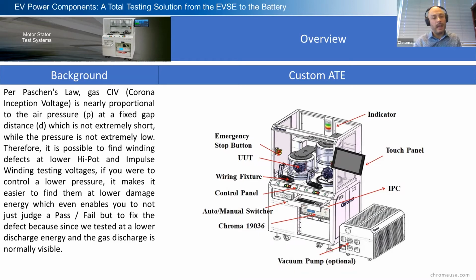Now, for the vacuum system, as you can read on the left-hand side, what we do with the vacuum system, I'm sorry, we put the motor in the vacuum. We lower the high pot voltage on it, right? And that helps you with the gas discharge where you would have an issue. So it makes it safer, right? And it allows you to look into which winding you had an issue on. Because typically what you do is you just do a high pot and see if you have a short, you measure leakage current possibly, an LCR meter, and that's it. But you will not be able to find a fault or find a defect and be able to fix it, right?